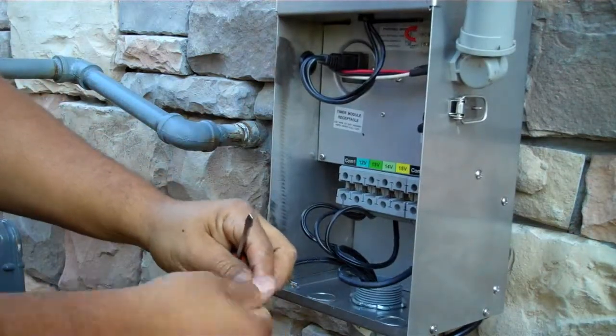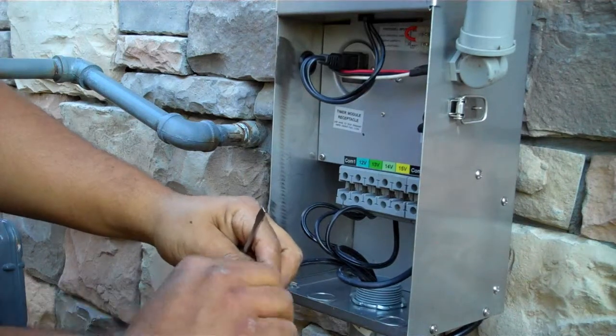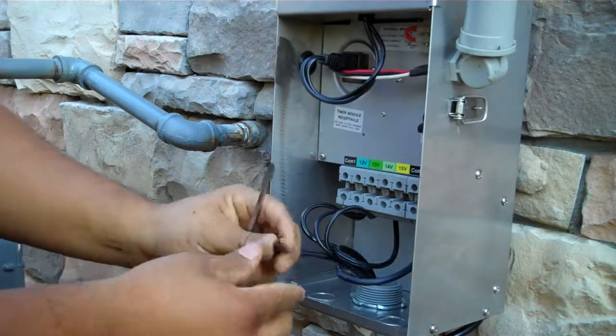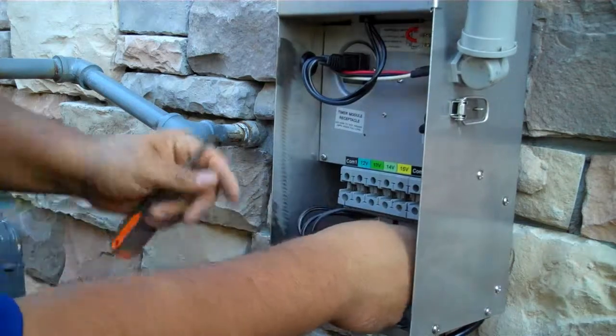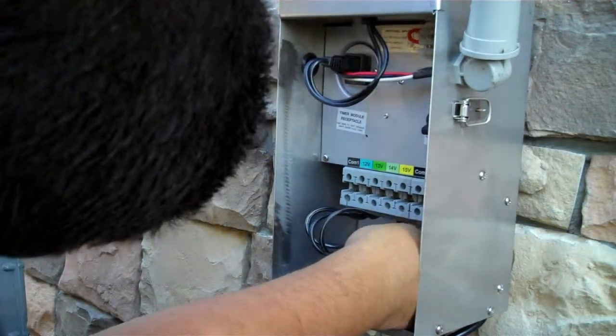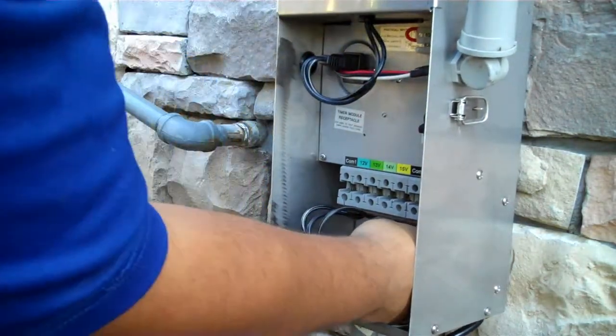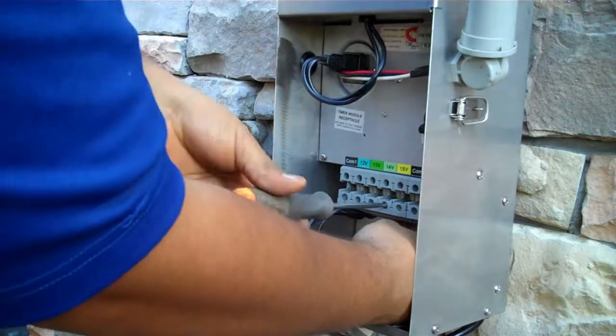When tightening the low voltage wires, make sure that the screw on the tap is tight. If the screws on the taps are not tight, this too can cause arcing. Achieving a proper connection is key when hooking up your transformer.